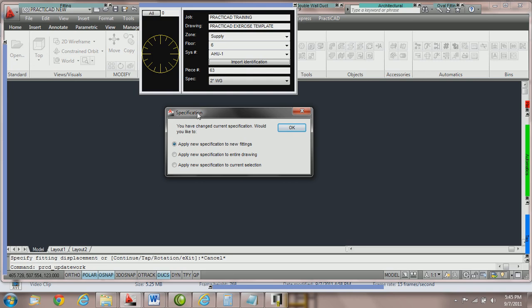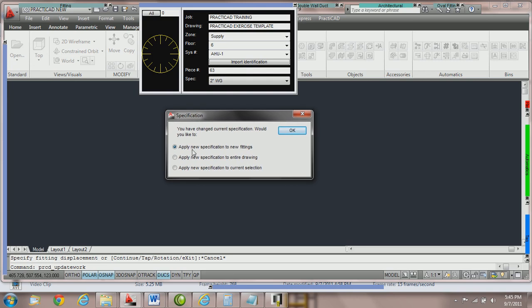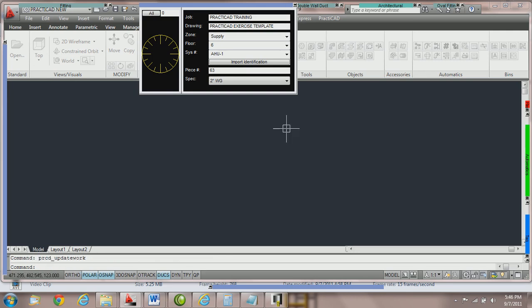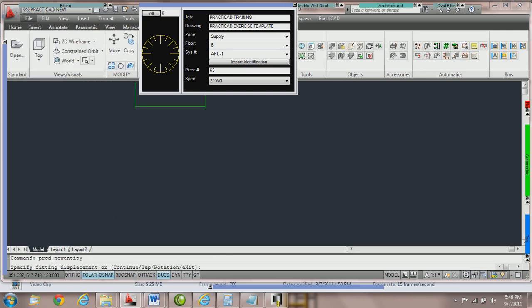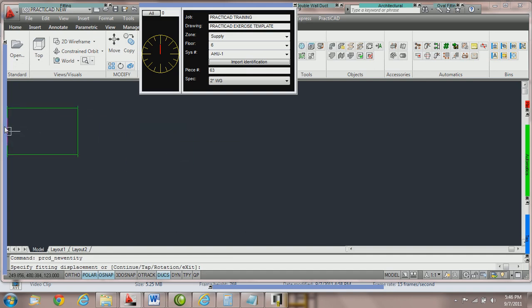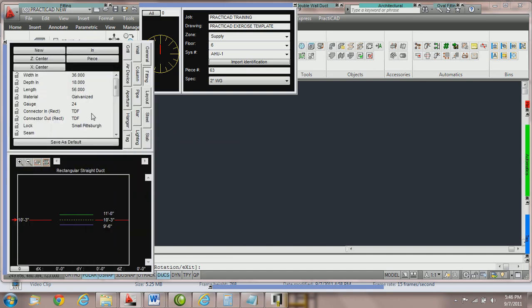We're going to get the dropdown menu saying should we apply new specs to new fittings, apply new specs to the entire drawing, or apply new specs to current selection. That means whatever is currently selected, we can now edit the spec. To start off, we're going to choose apply new spec to new fittings and press OK. Now when we go to grab a piece of duct, you can see instantly that the spec is working on the fitting. It's added the proper connections and locks and all the other technology data.